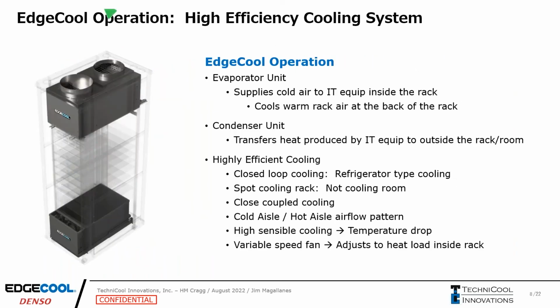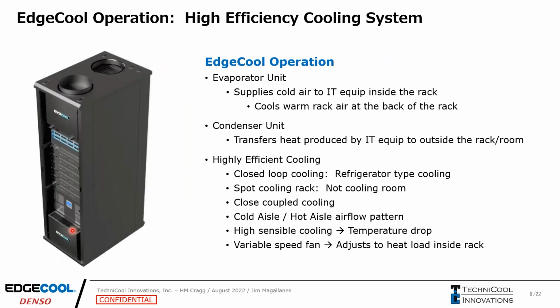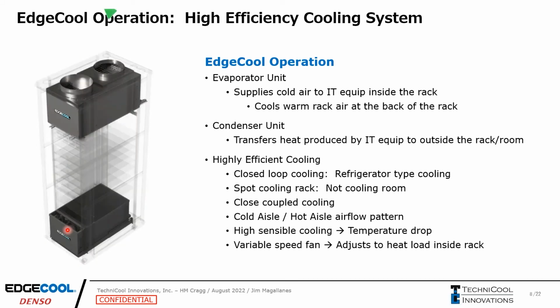And so how this operates, I mentioned that the evaporator goes into the bottom of the rack, and this is what's supplying the cold air down here. As you can see, it's blowing up cold air in the front of the IT equipment. The IT equipment has their own internal fan system, so they draw in that cold air that's situated right in front of their rack. And as it goes across their internal circuits, it heats up the air and exhausts it out the back. That hot air in the back is then captured down into the evaporator unit again, and just starts that cycle off again.